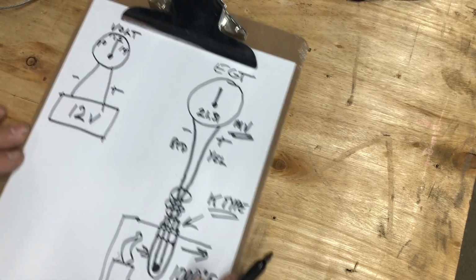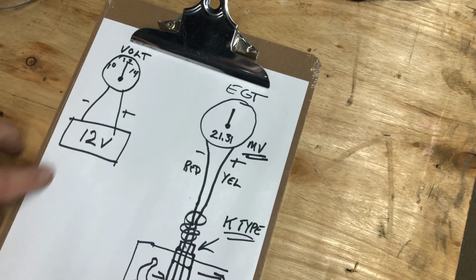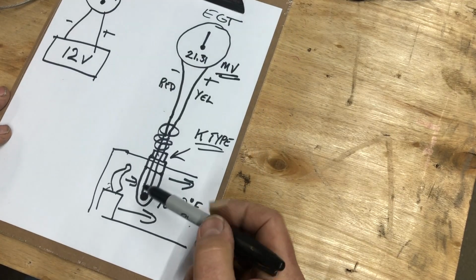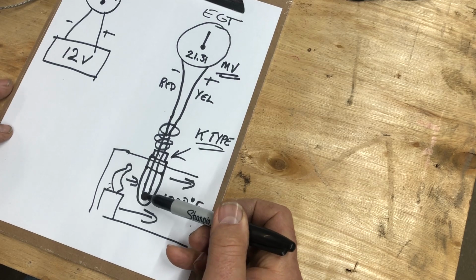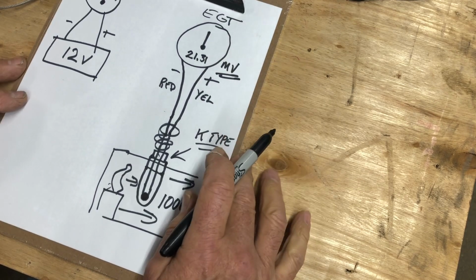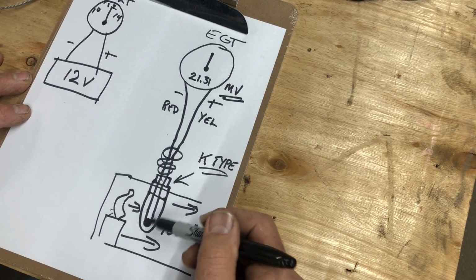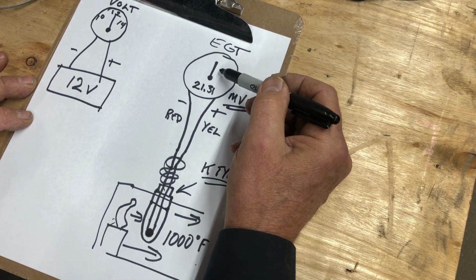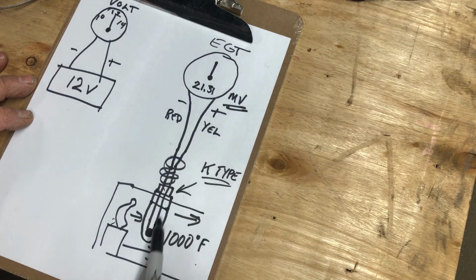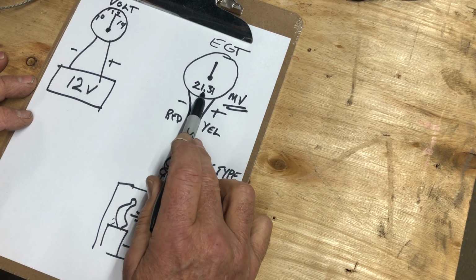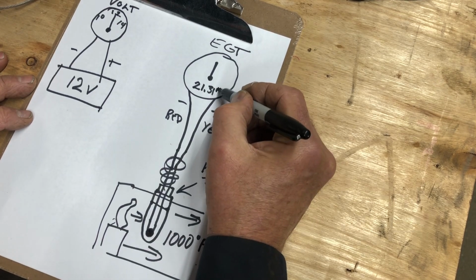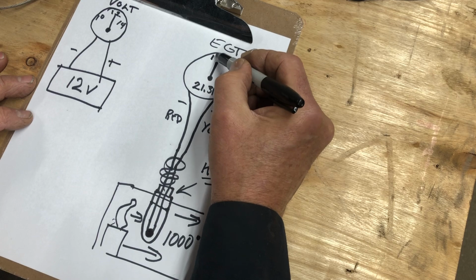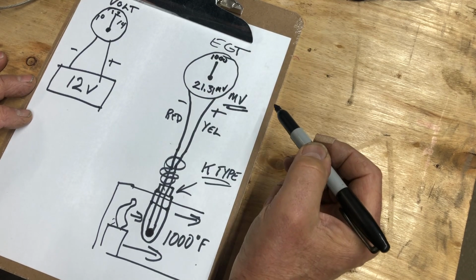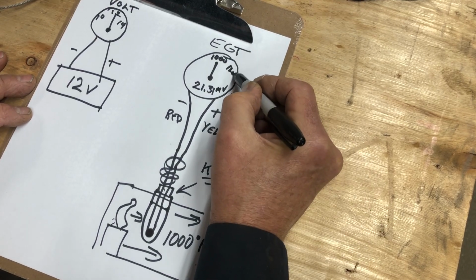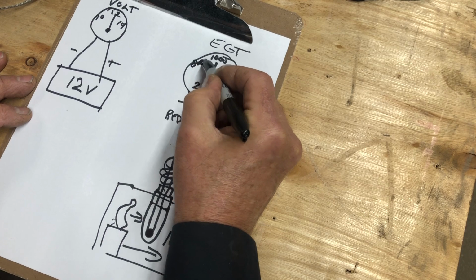It can't produce the power you'd get out of a car battery, but with temperature, it changes how much it produces. So they've calibrated this instrument so when it receives 21.31 millivolts, it's calibrated to say 1000 degrees. And then it'll be like 1200 over here and 800 over there.